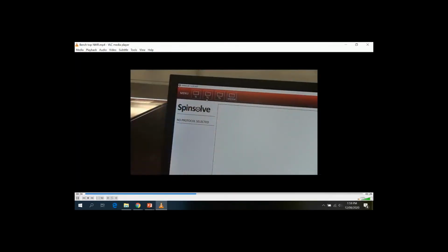So you have your tube there and it has a holder that it needs to sit in. So it gets placed into the top of the machine. And then you go to your computer. You click your shim in the systems and it runs like a background check. It sort of calibrates. And then once you get a successful shim, you then can put your sample in.